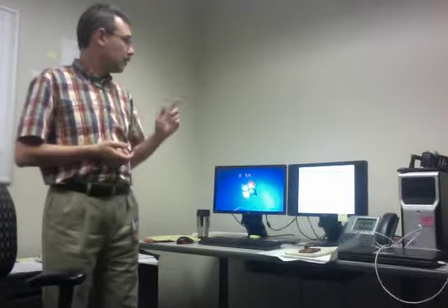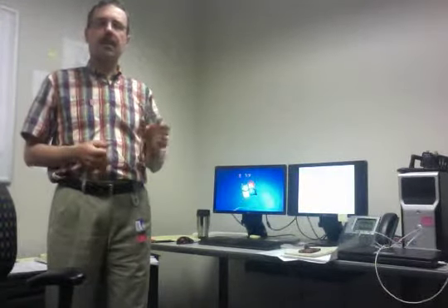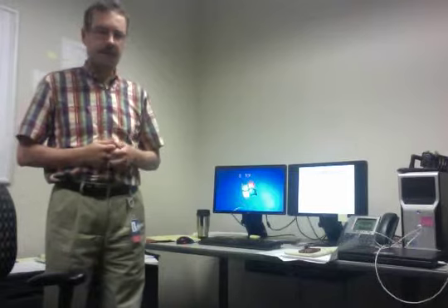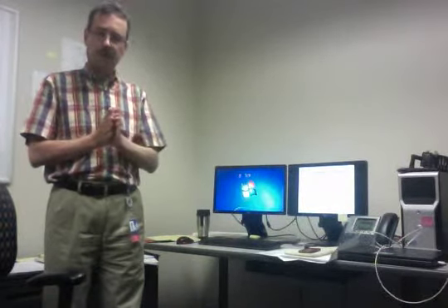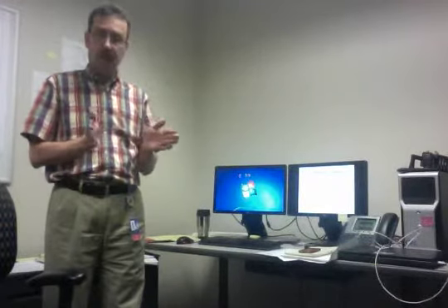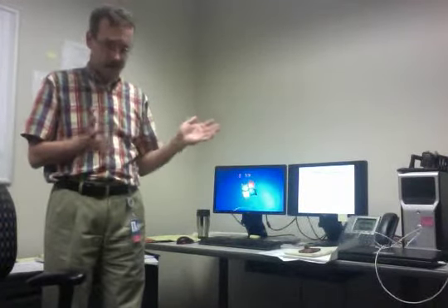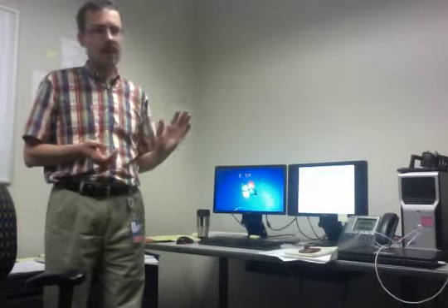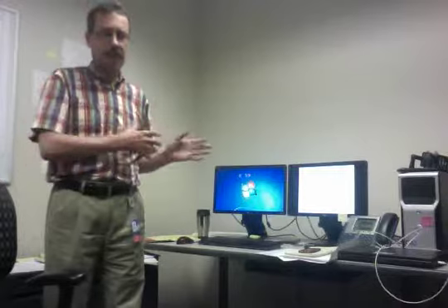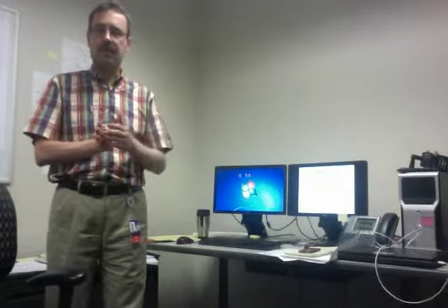I'm coming to the end of my talk, so I thought I'd run through just a couple more things real quick before I wrap everything up. No matter the size of the capacitor bank, they always take 5 minutes to discharge. So if your circuit switcher pulls that capacitor bank offline and is immediately followed by a voltage sag, you're going to have to wait 5 minutes before that capacitor bank can be safely brought back online.